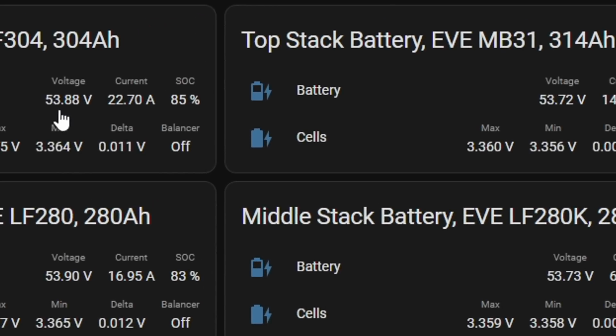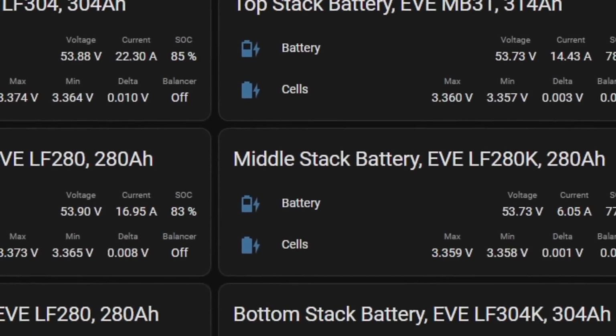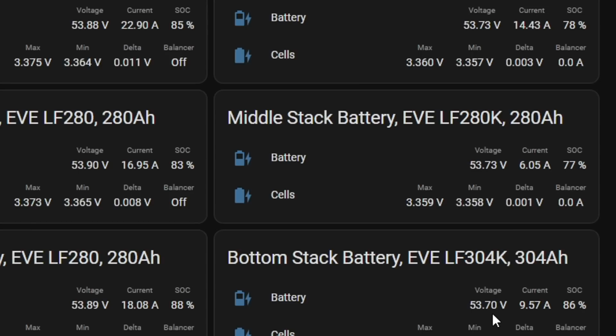We've got 53.88 volts here charging voltage, and 53.73 over there. Looking at these numbers, this is the battery with the lowest voltage—so it has most of the voltage drop—and this is the one with the highest. So, as expected, the battery shelf is actually charging faster, because it has a better connection to the source, to the charger, than the Gobel Power.